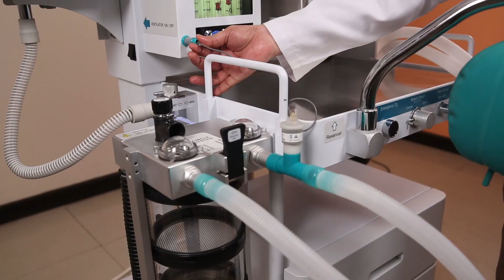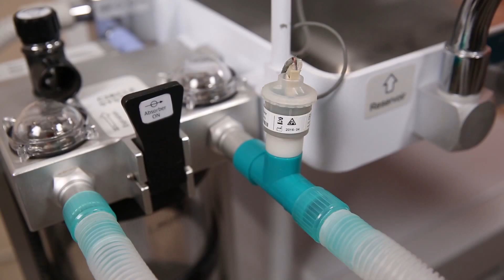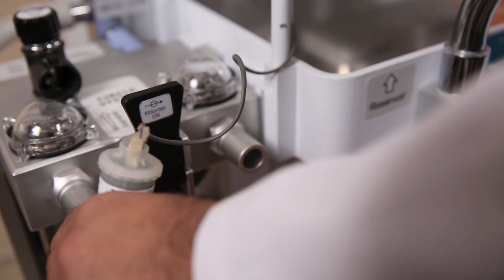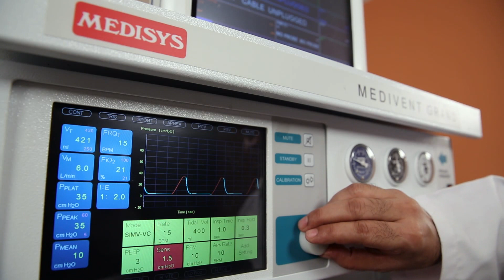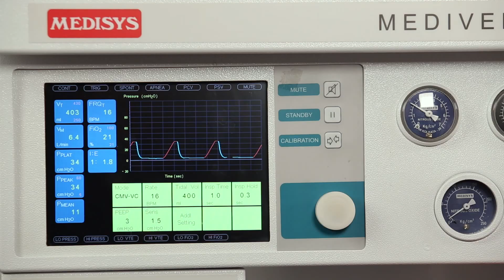To check the oxygen flow, we have a very sensitive oxygen analyzer incorporated in the machine. It is externally visible, and the sensors can be put in the inspiratory limb of the circuit or in the expiratory limb of the circuit. By that I mean they are interchangeable. The machine offers you a very easy way of selecting the mode of ventilation. With a flick of one switch only, you can go on changing from one mode to another, which is very easily visible, and it is also depicted in the data displayed on the screen, and it will also show the changes it produces on the machine parameters on the screen.